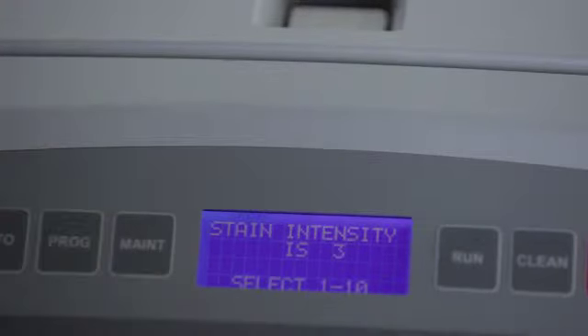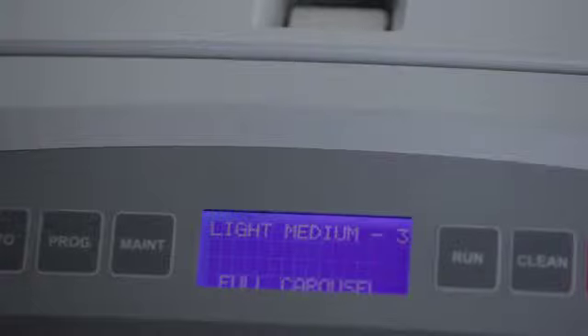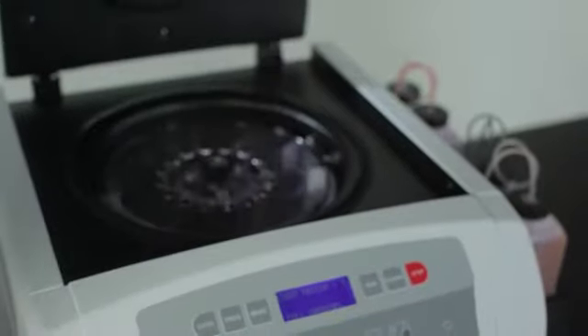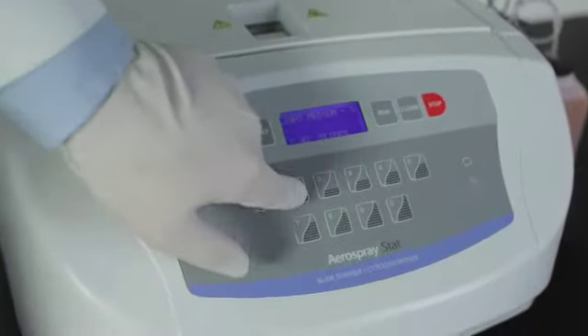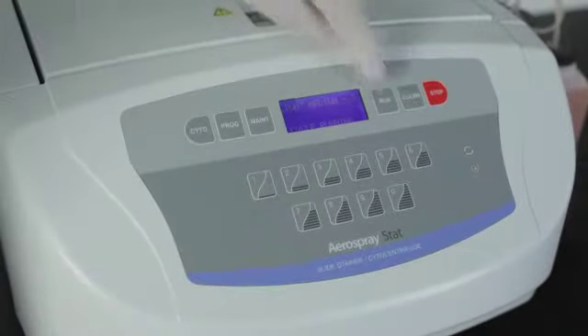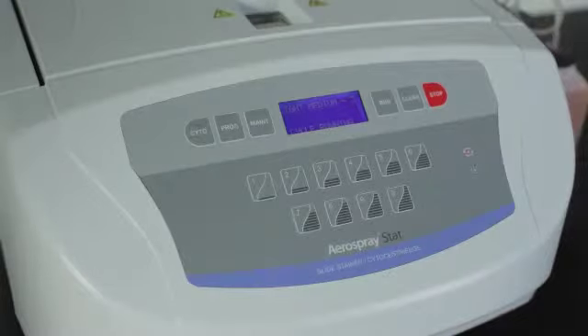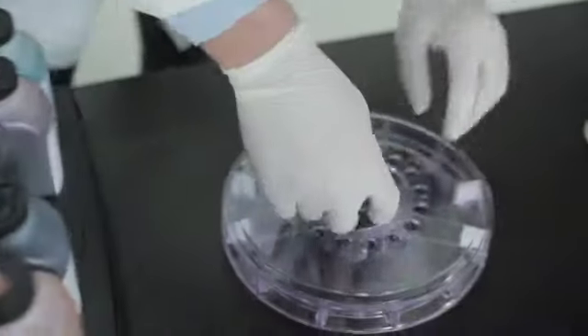After the program has been selected and slides loaded into the carousel, simply put the carousel in the stainer, close the lid, select the number of slides to stain, then press run. After 4 to 6 minutes, depending on the intensity, come back to the stainer. Open the lid, remove the carousel, and then remove the slides. The slides are now ready for the microscope.